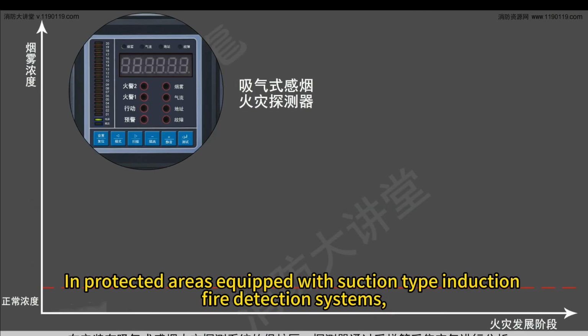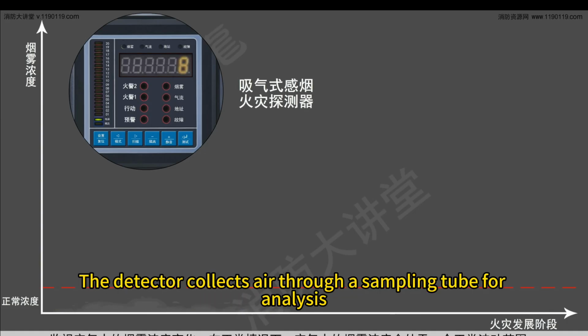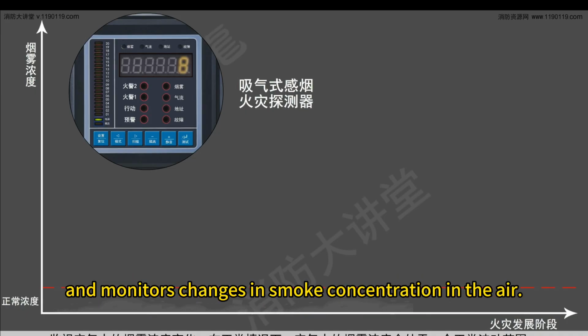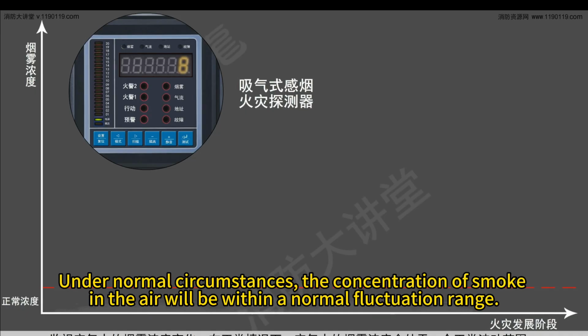In protected areas equipped with suction-type induction fire detection systems, the detector collects air through a sampling tube for analysis and monitors changes in smoke concentration in the air. Under normal circumstances, the concentration of smoke in the air will be within a normal fluctuation range.